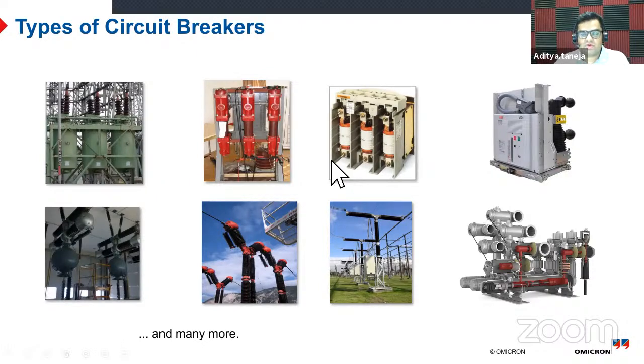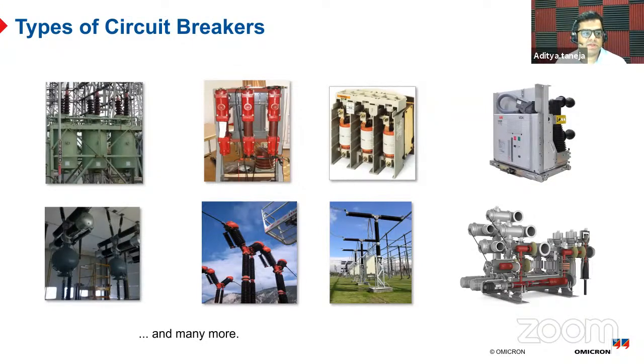So what I'm covering today is AC high voltage, which already gives you a window. High voltage means, in the IEC definition, everything above 1 kilovolt, and AC means that it is not DC. So there are low voltage breakers, which I'm not going to talk about, and DC breakers also, which I'm not covering. Those have a different technology altogether, and need a different way of testing and maintaining them.